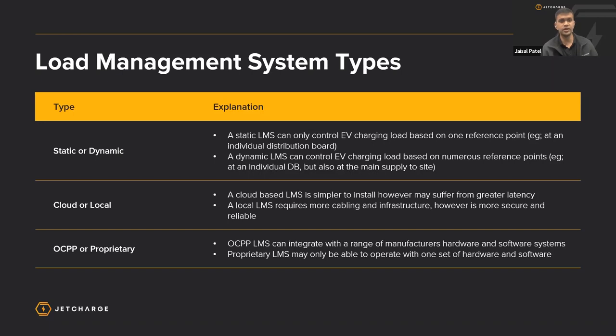The second way of doing it is what's called a dynamic load management system, where you have two or more reference points where you can actually monitor the incoming supply to the site to not exceed a particular number, whether it's the max rating of the distribution board feeding the entire site, or it may be the supply offer that you received from the authorities when you made your DNSP application.